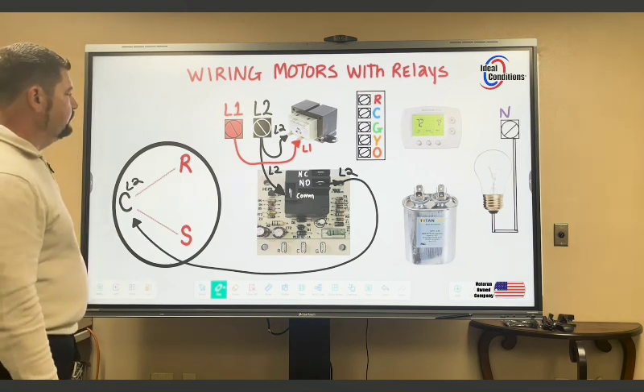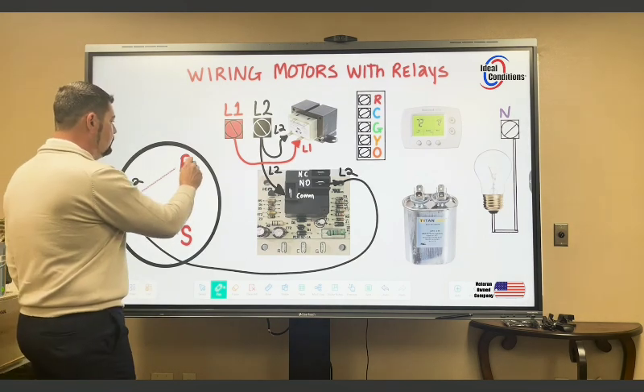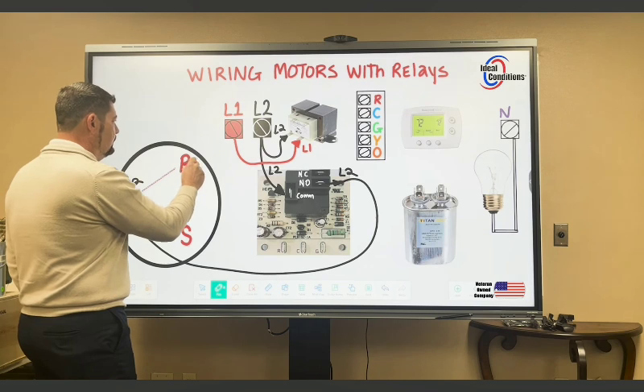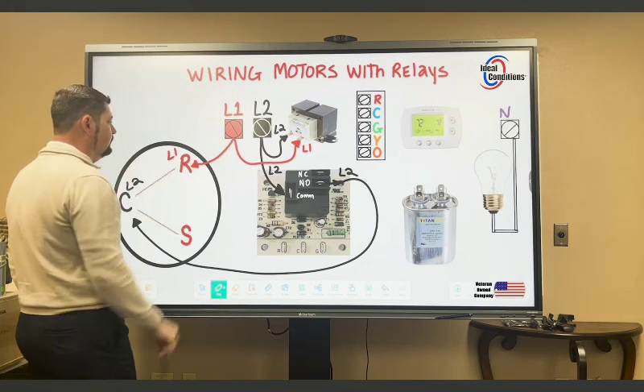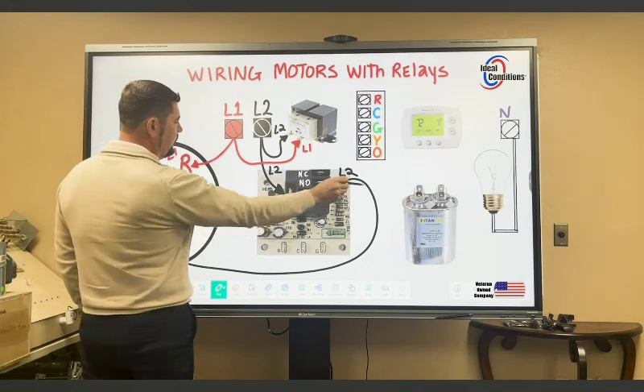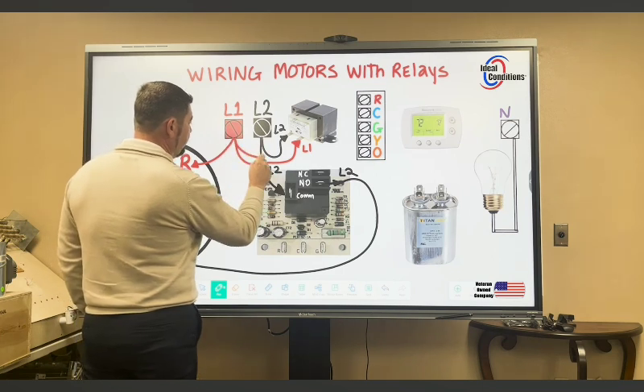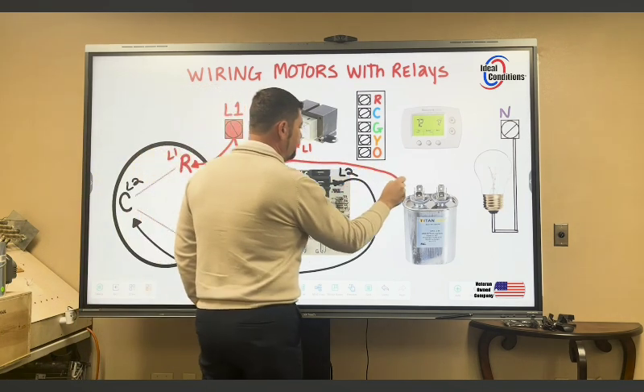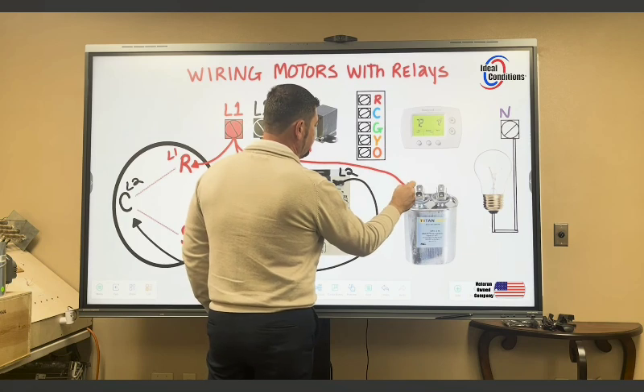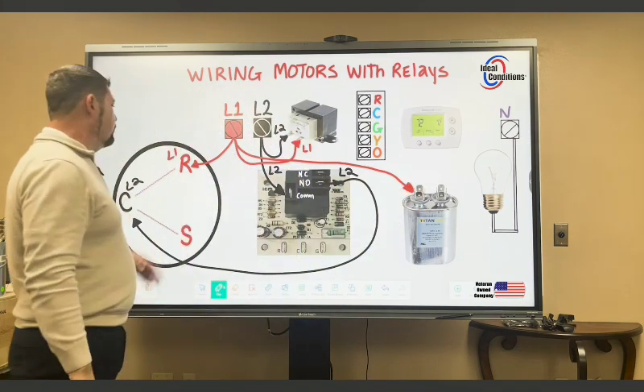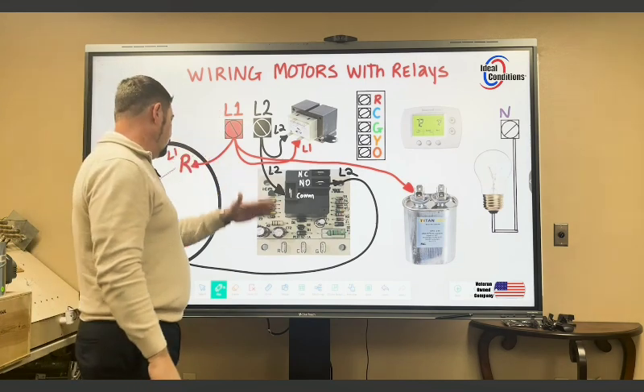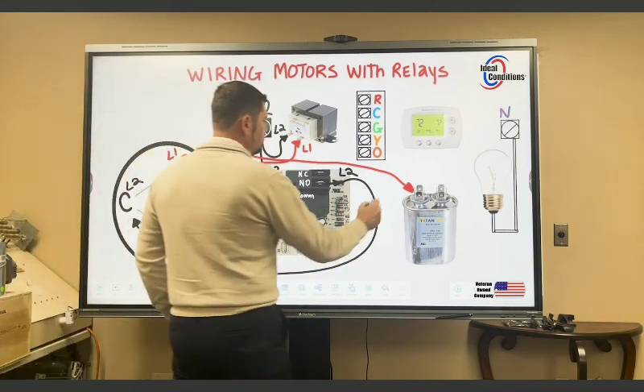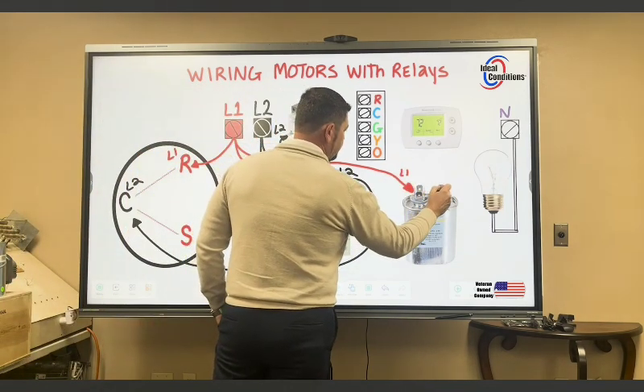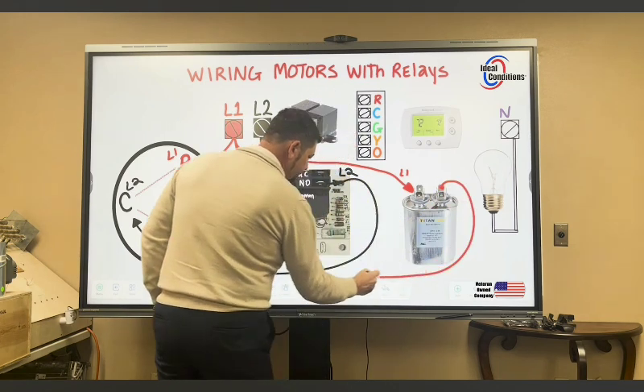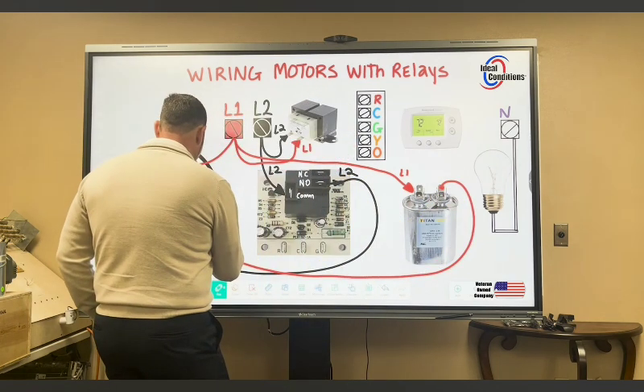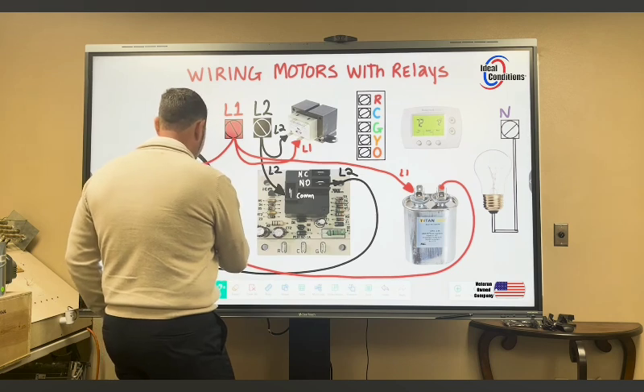Where else does L1 have to be? Okay, L1 needs to be on my run winding. Okay, it needs another leg of power. We're going to go ahead and label that. And then L1 also has to be over at my capacitor. And the reason why we have to do it that way is because if I used L1 for my run winding, then I also have to use L1 for my start winding. We're going to go ahead and label this. We're going to come out of here as an output, and we're going to come over to our start winding. And we're going to go ahead and label it.